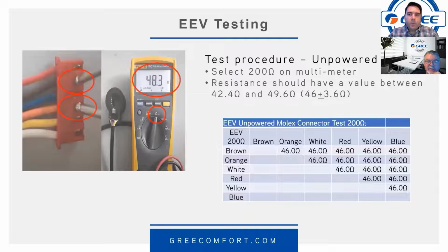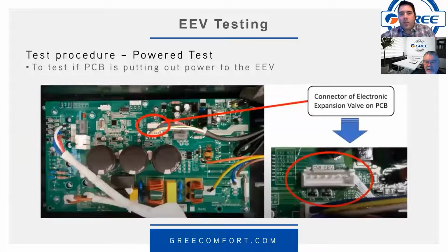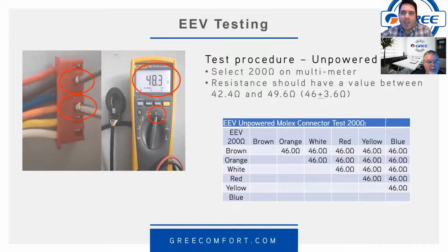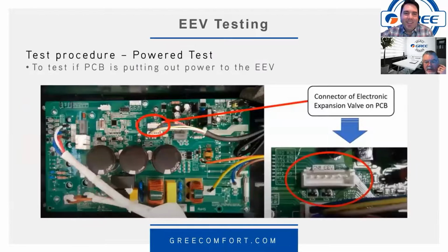So this is another unpowered test. Select 200 ohms on the multimeter. Resistance should be 46, plus or minus 3.6, so somewhere in this range. And this gives you the wires to test across and what the reading should be. It looks like someone needs some needle point adapters for their meter on that last picture. Yeah, no doubt. No question. Yeah.